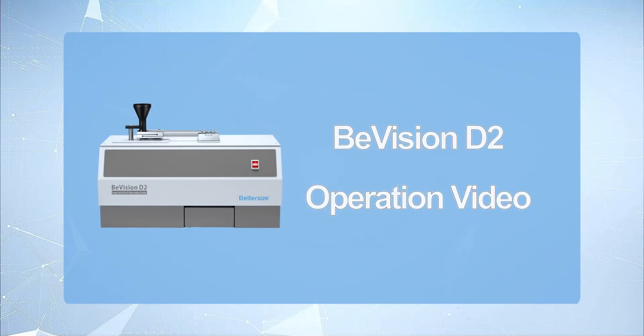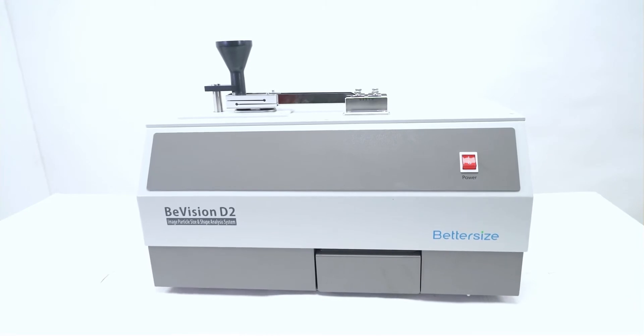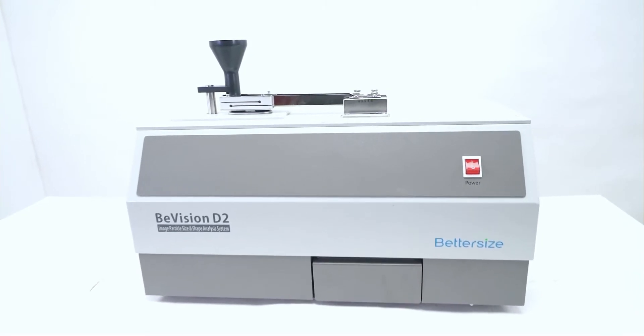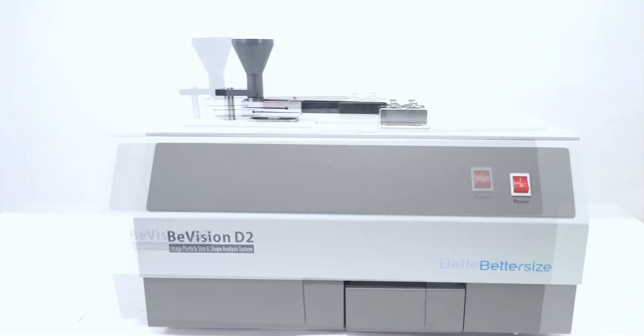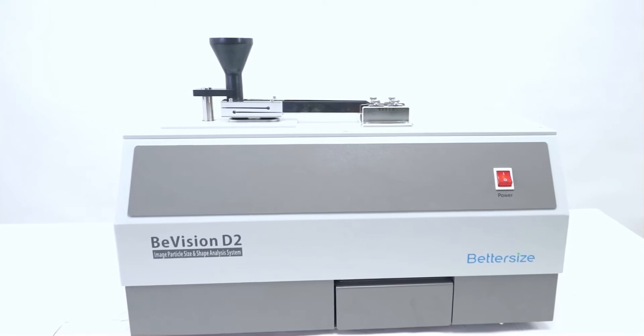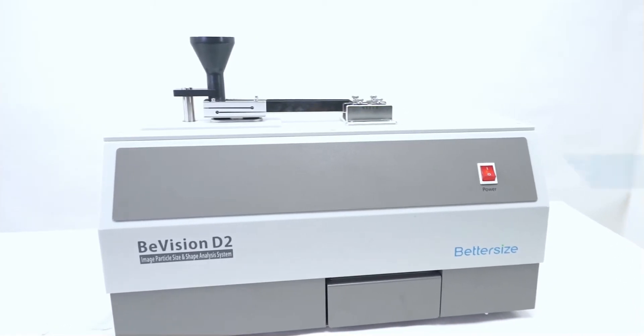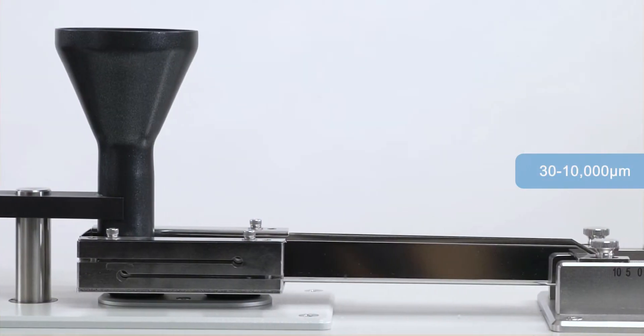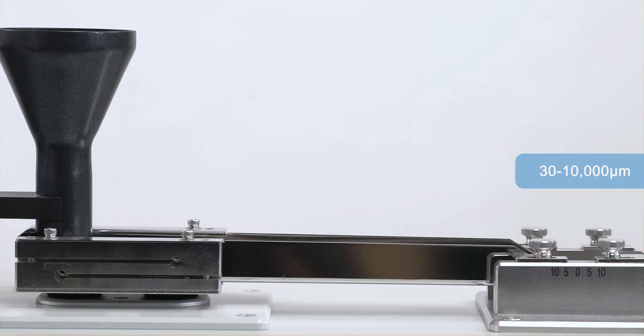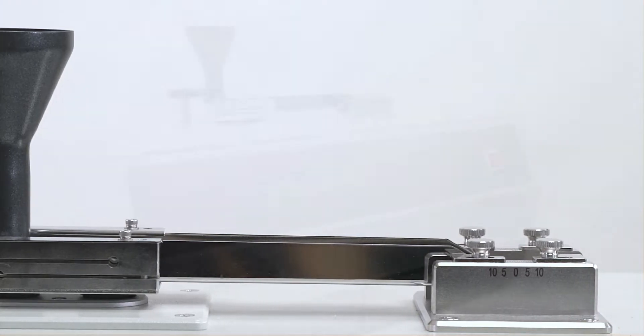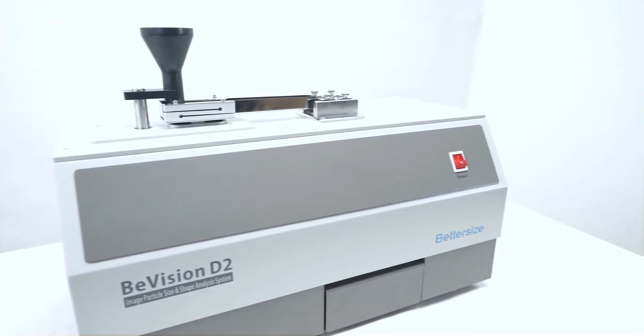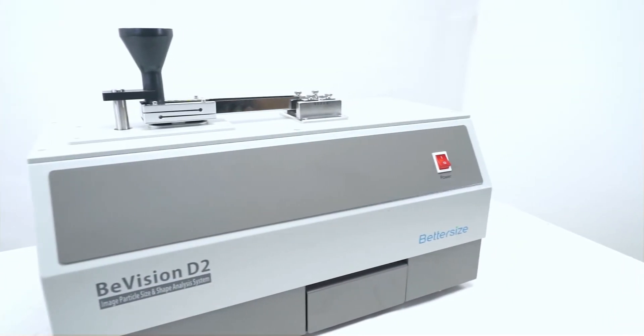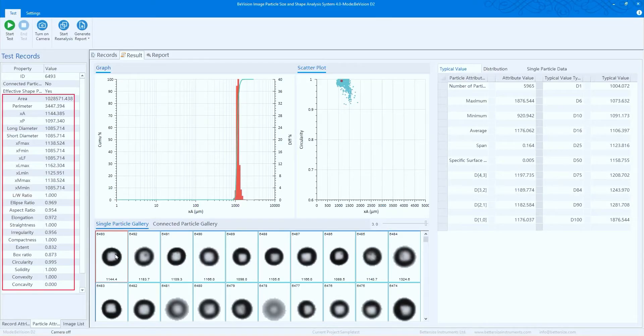The BeVision D2 is a dynamic image analyzer providing particle size and shape analysis of dry, high flowability powders or granules in a range of 30 to 10,000 microns. The BeVision D2 reduces tedious analysis time by providing rapid, detailed analysis of thousands of individual particles from 24 different aspects, which allows fast visual and statistical data interpretation.